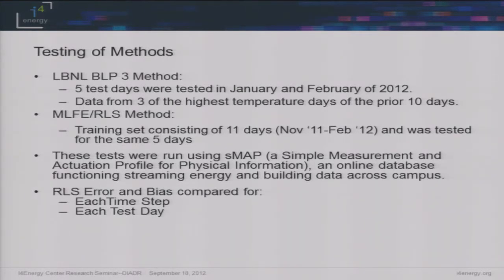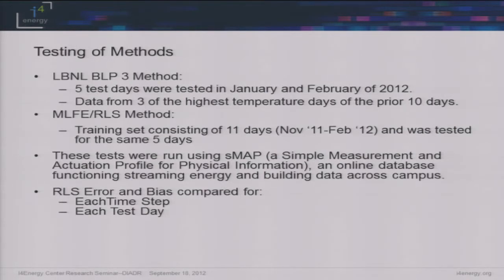For testing these methods, we used five test days in January and February. For the BLP 3 method, we pulled the three highest temperature days of the previous ten for each of those days. For our method, we used a training set of data, making sure the training sets didn't overlap with the test days. We used SMAP — as Dave Kohler was talking about earlier — to pull data from the server we have running. We then calculated the RMS error and bias and compared them for each time step on each test day.